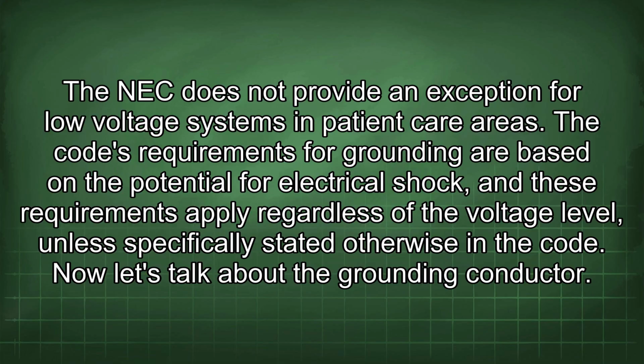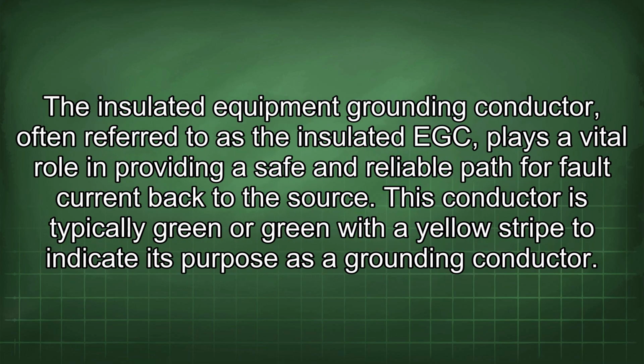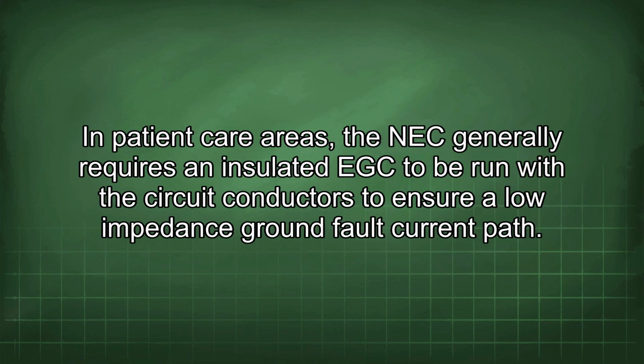Now let's talk about the grounding conductor. The insulated equipment grounding conductor, often referred to as the insulated EGC, plays a vital role in providing a safe and reliable path for fault current back to the source. This conductor is typically green or green with a yellow stripe to indicate its purpose as a grounding conductor. In patient care areas, the NEC generally requires an insulated EGC to be run with the circuit conductors to ensure a low impedance ground fault current path.